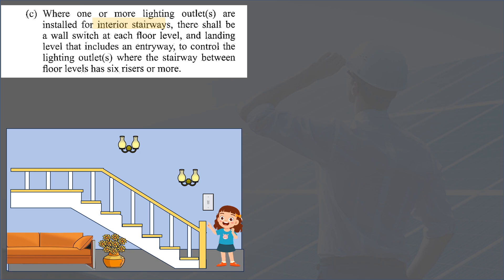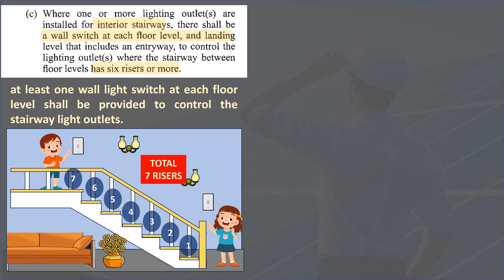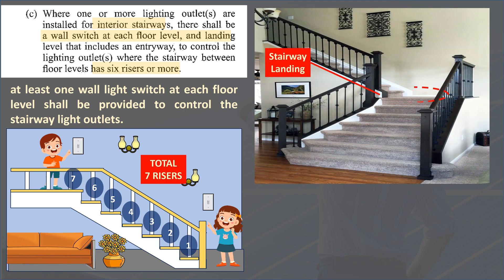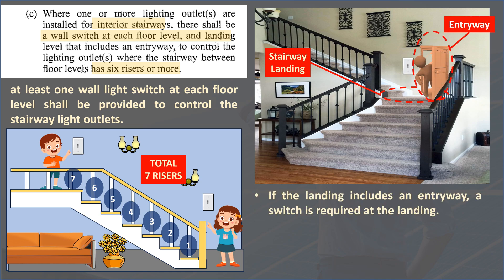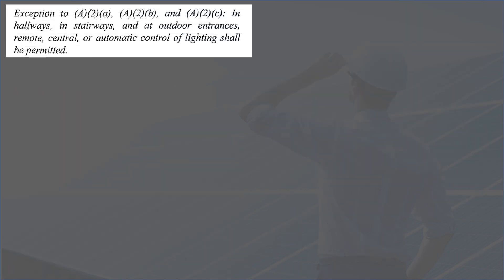If interior stairways have six or more risers between floor levels, at least one wall light switch at each floor level shall be provided to control the stairway lighting outlets. If less than six risers, at least one light switch is required. Some stairways have one or more landings between floor levels. If the landing includes an entryway, a switch is required at the landing. A landing with no entryway shall not require a switch and will be considered as one of the risers of the stairway.